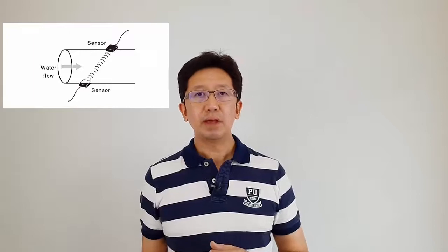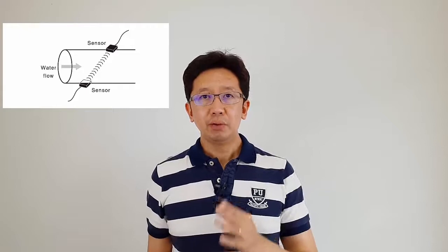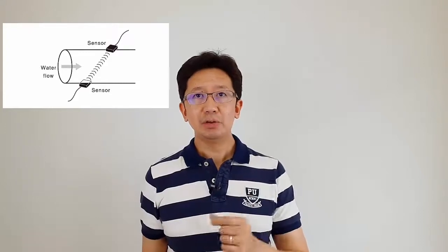Ultrasonic flow meters use an ultrasonic pulse which is beamed into the pipe and reflected by inclusions. The ultrasonic meter is frequently used as a clamp-on device which can be fitted to an existing pipeline. However, it detects the velocity of only a small region across the pipe section, so its accuracy is not so good. The limitation of the ultrasonic flow meter is that it is not suitable for dirty fluid or dirty gas service, because the ultrasonic reading uses the reflection phenomenon.